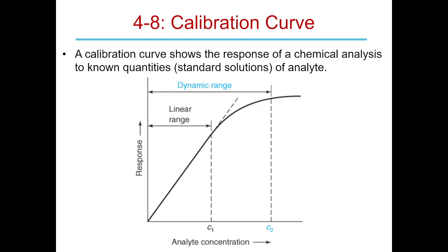It was like a $500,000 instrument. And every sample always had to be diluted significantly because it was very, very responsive. It could pick up even small differences in concentration. But its dynamic range was actually fairly small, and it could actually get damaged if you put in too much. The signal would damage the internal components.